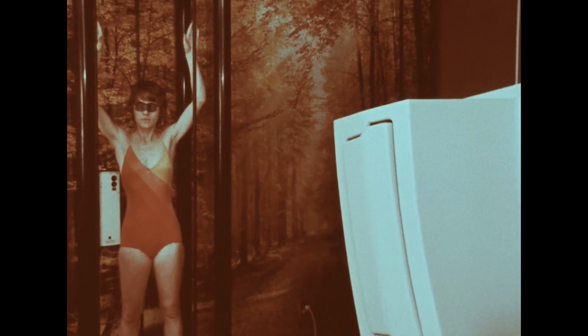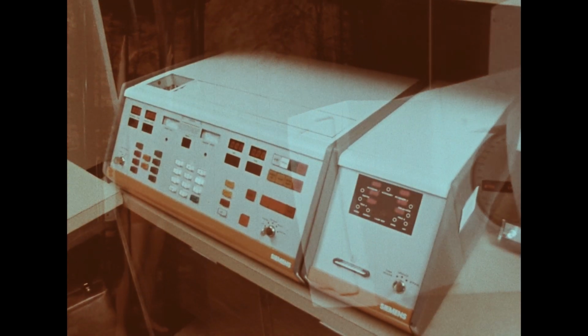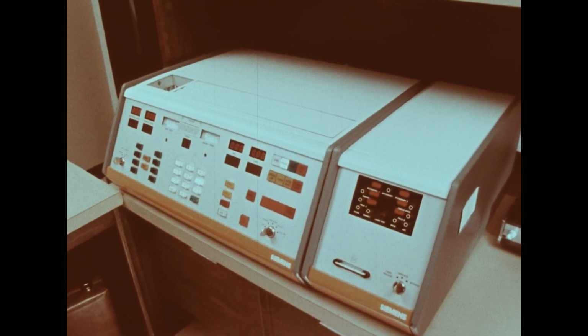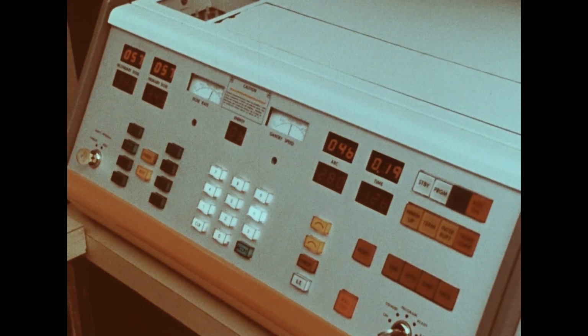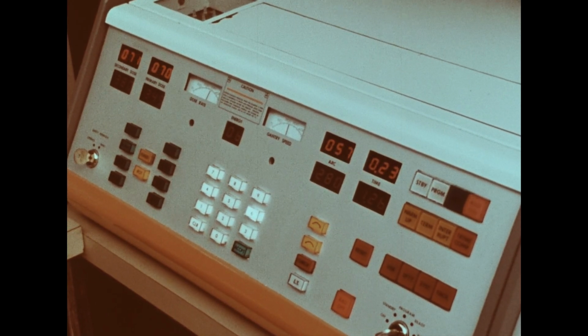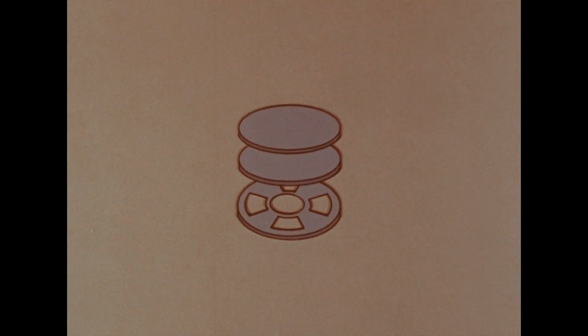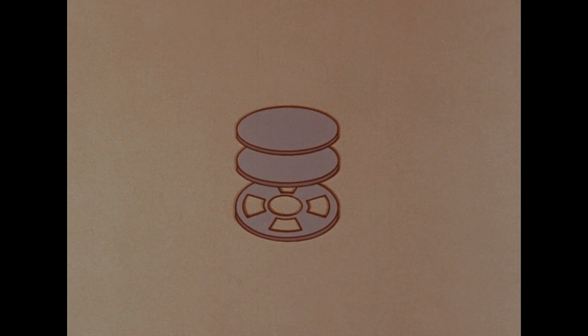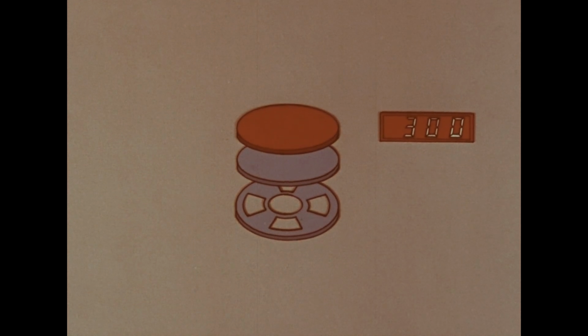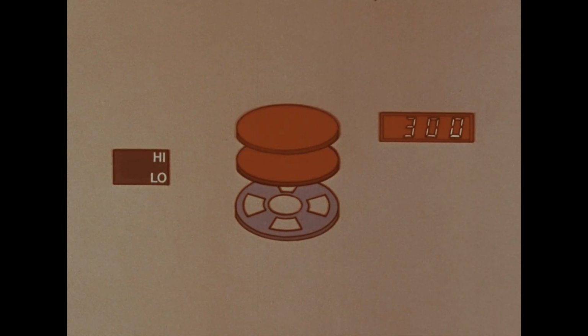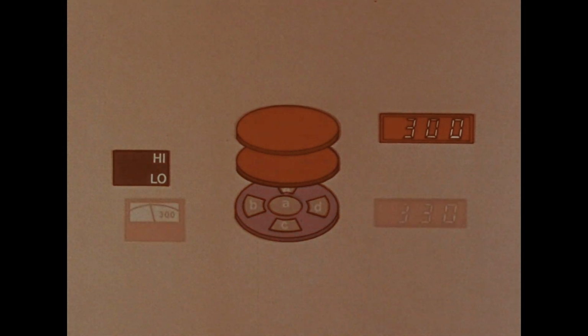And what about safety precautions against radiation hazards due to human or machine errors? The Mevatron has an almost foolproof dosimetry system for the photon as well as the electron beam. Any failure of the controlled parameters causes an immediate cutoff of radiation. The primary dose ionizing chamber measures total radiation coming out of the target or the dual foil system. Once the amount of radiation has been reached, the chamber gives out a signal to discontinue radiation. If high or low dose occurs, an interlock mechanism shuts off radiation.